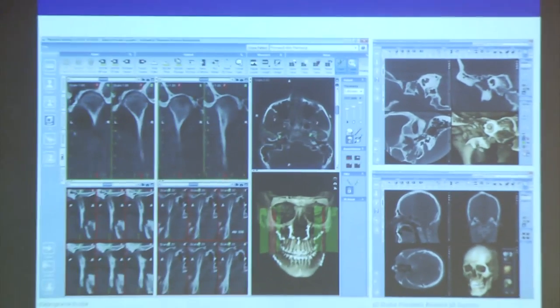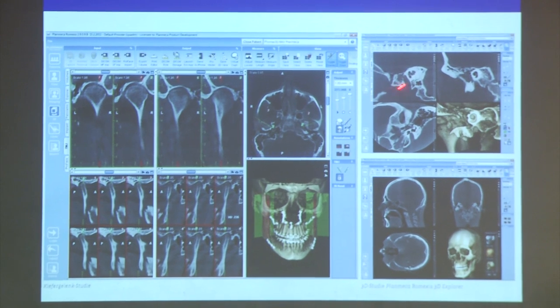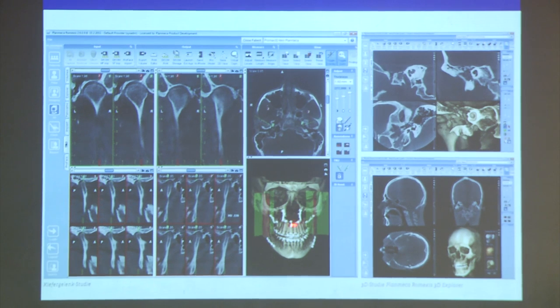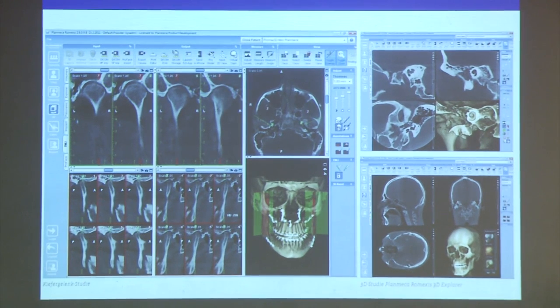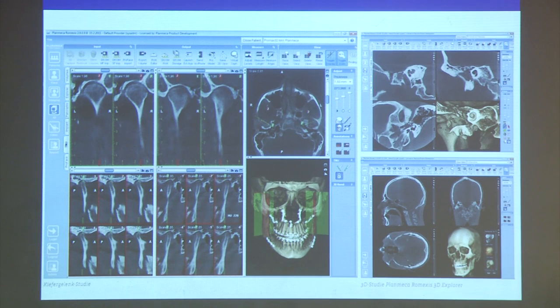What image quality can we expect today? You have the same image quality in all reconstruction levels. The level of metal artifacts — and it was a very good question from the audience, because we had two TMJ prostheses and heavy metal work in a face — the level of metal artifacts was acceptable, but they were there. If you do a CT scan throughout this, it will destroy your image. So they are there but they are less.